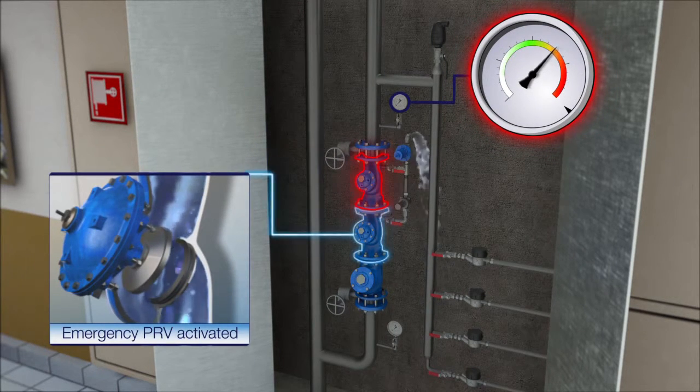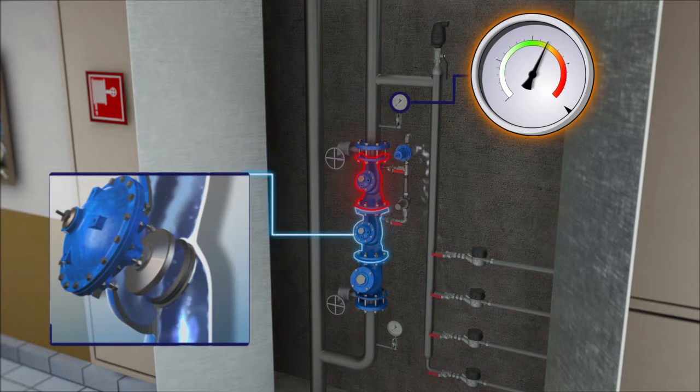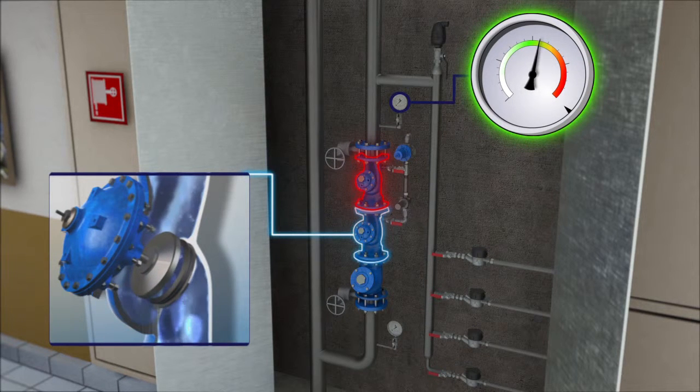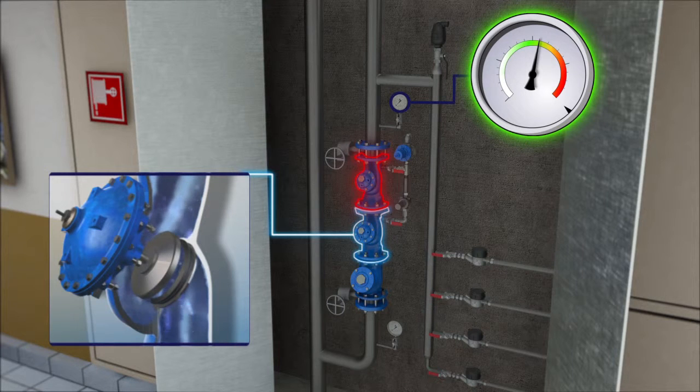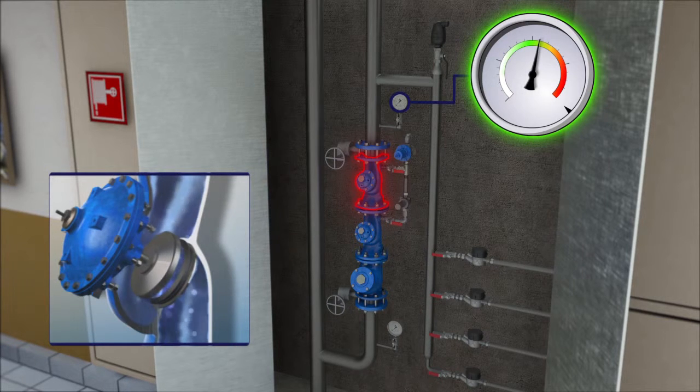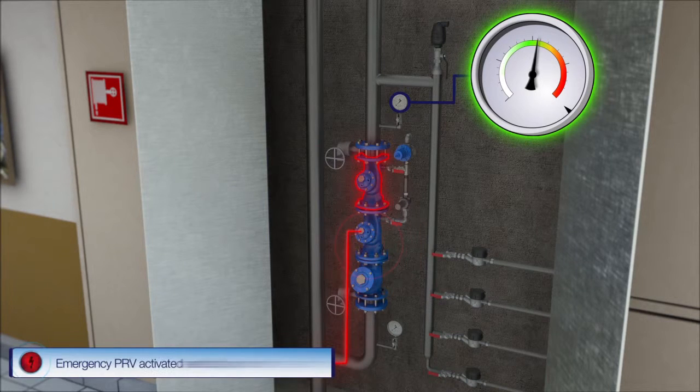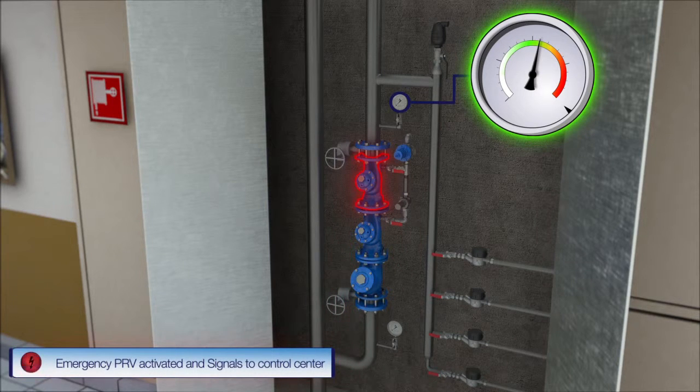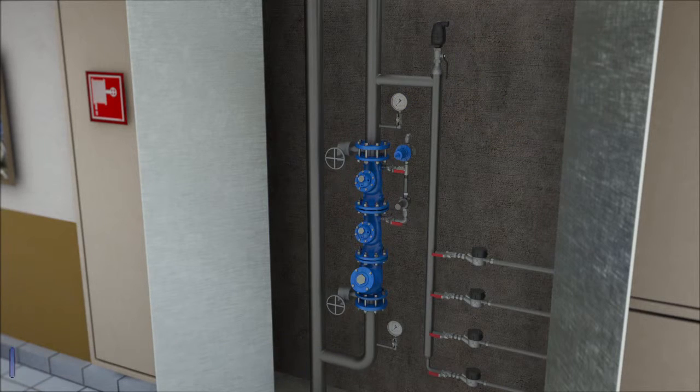The backup pressure reducing valve senses the undesired excessive pressure and kicks into operation, keeping the system in slightly higher but safe downstream pressure setting. A fault signal is sent to the building's control room by the limit switch, notifying the building's service team to address the problem.